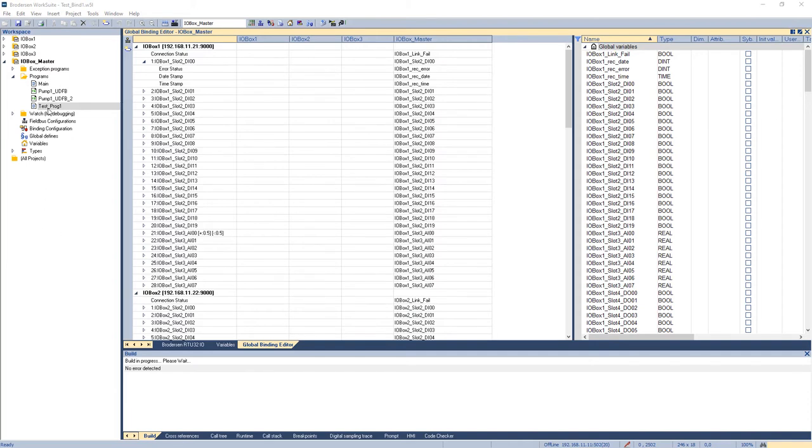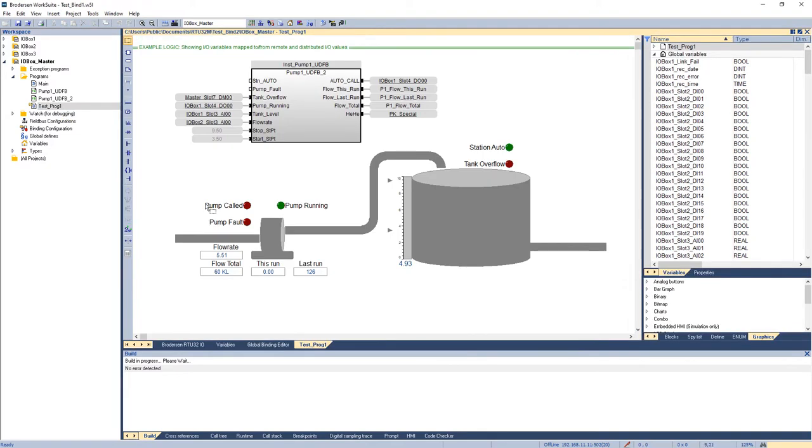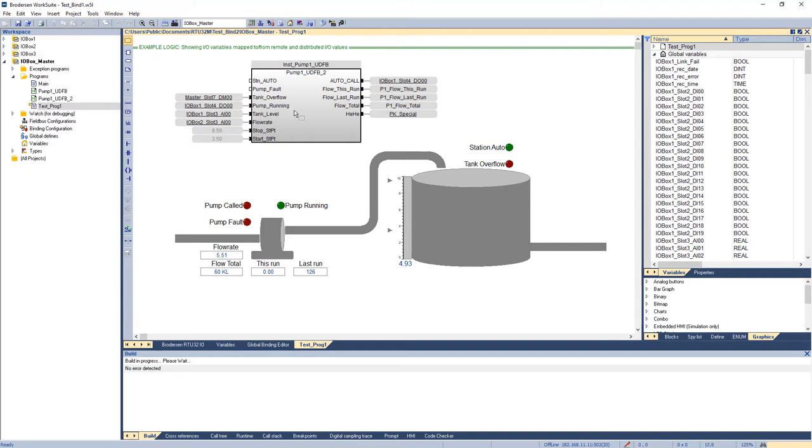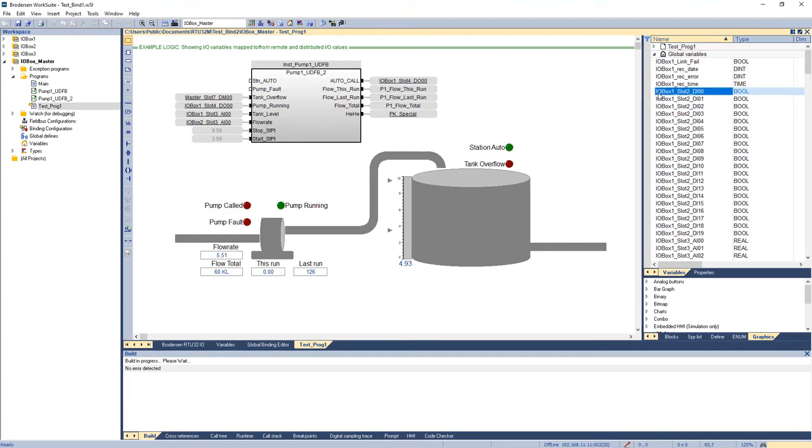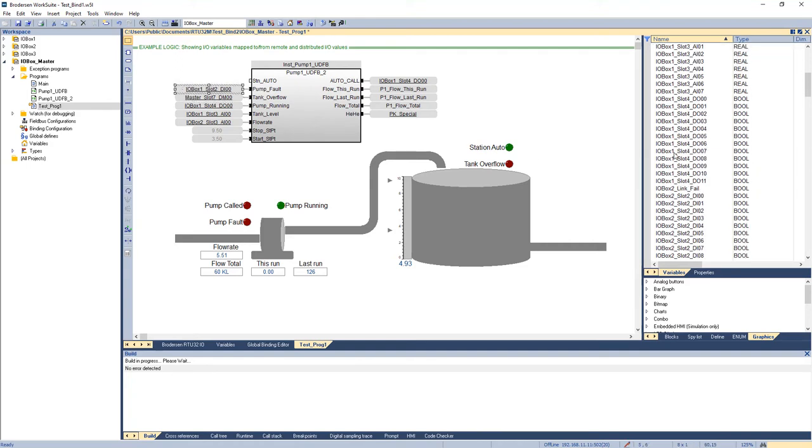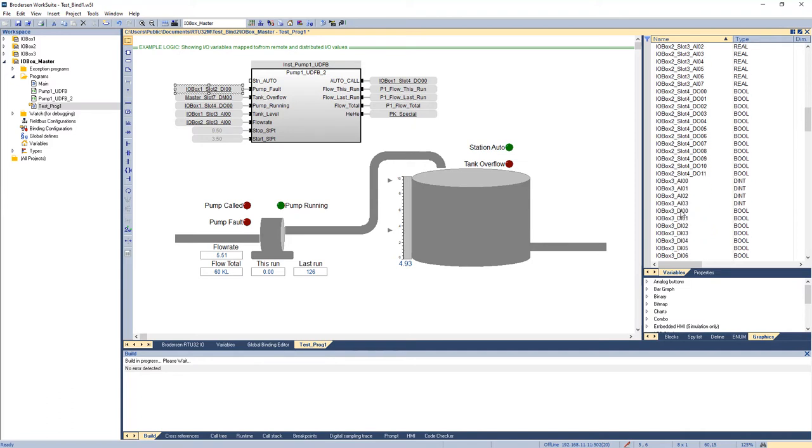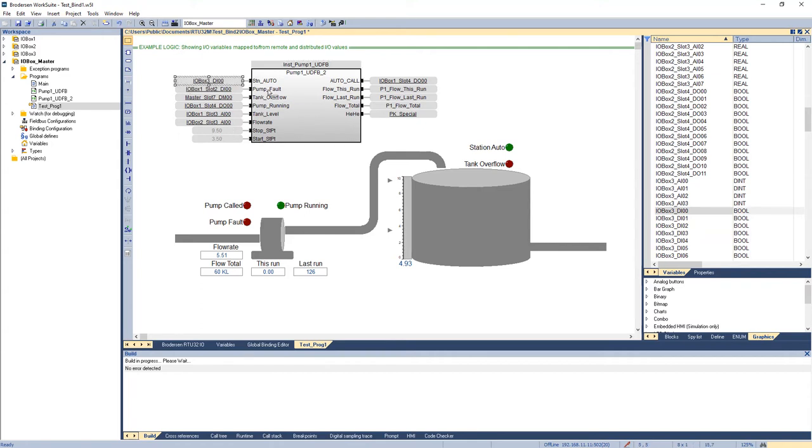So the last part of the process is just prove we can associate some logic to all of this remote I/O that we have. I've been building a little logic application. Just got a few final things to finish. So I've got a little pump controller function block. I've dragged in some remote I/O. So we've got the flow rate signal coming off I/O Box 2, we've got the tank level off the analog of I/O Box 1. We have a pump running presently tied to the pump call so I don't have to remember to turn the pump on when we ask it to run. We have the tank overflow coming from the master's I/O module. So let's drag in the pump fault and the tank overflow. Maybe we'll take the pump fault here off I/O Box 1, we'll drop that variable in. And we'll zip down to I/O Box 3 and take its first digital value, drop that on there, that can be our station auto.